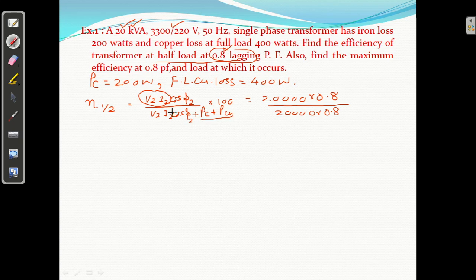So this will be at full load, if you want to find it at full load. But I have been asked to find the efficiency at half load. If it were full load, you can do it like this: plus what, iron loss is 200 watt, plus copper loss is given as 400 watt, multiply by 100. So this is at full load. If you are asked to find the efficiency at full load, you can use this formula. Clear? Then you can write it as 16,000 upon 16,000 plus 600, into 100. In this way you can find the efficiency at full load.